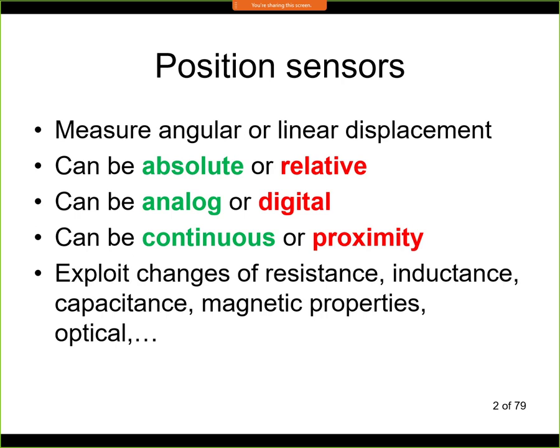The advantage of proximity sensors is price, because in many applications you really don't need info about the distance. A proximity sensor may cost something like 50 to 100 US dollars, while a continuous sensor would be something like 200 or 300 US dollars. There are many applications where you just need to know that the object is there, so in that case you will use a proximity sensor.